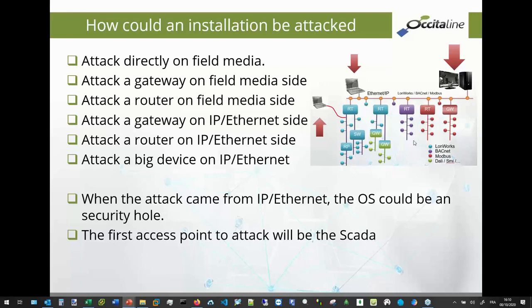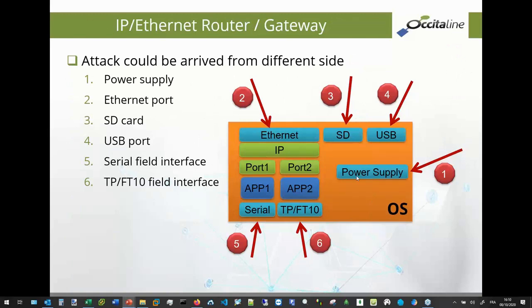The first access point was or will be the SCADA. Why? Because the SCADA is a computer. In many cases, it's a Windows computer, and Windows is known by a lot of hackers. If the SCADA can be modified to create a modification, an update or a destruction of your installation, you can't protect that. It will be almost impossible to protect your installation. This point about the SCADA is very important, and the network can be saved only if you remove the SCADA.